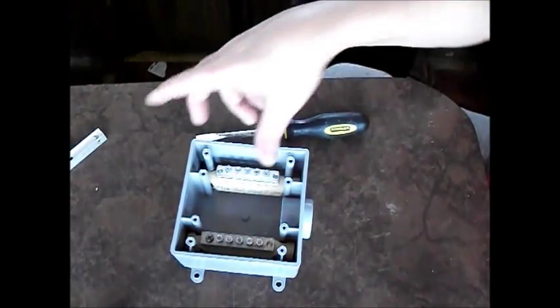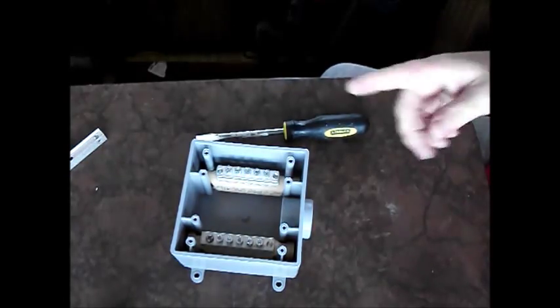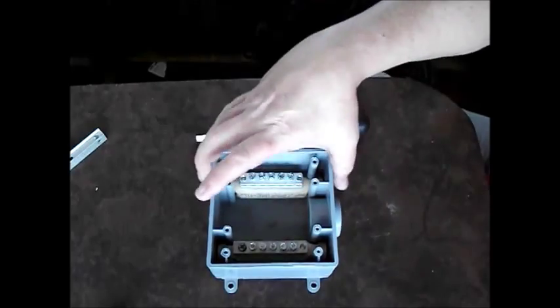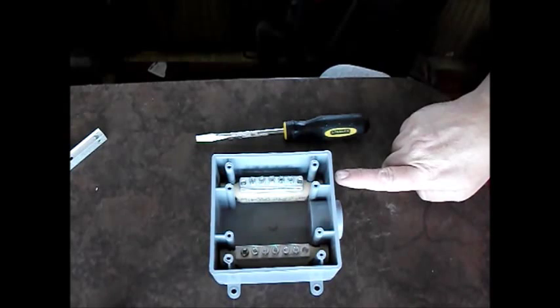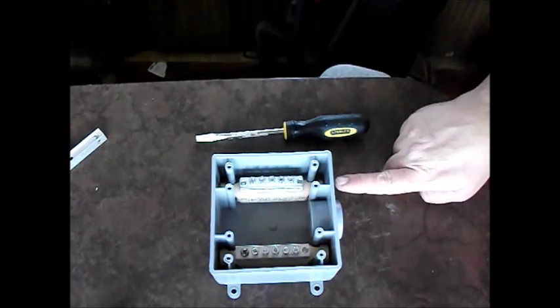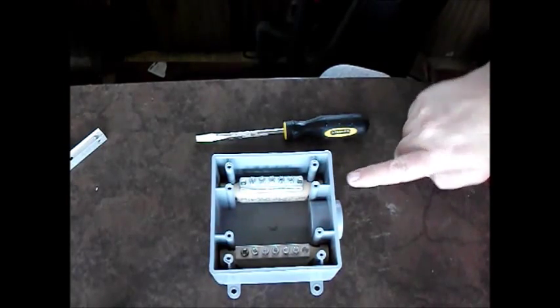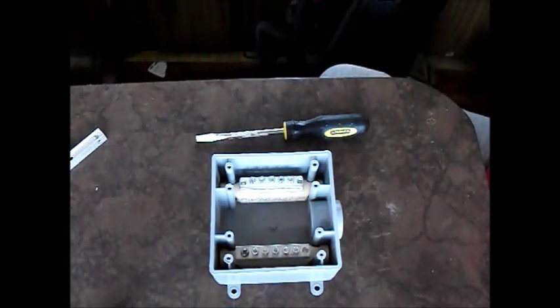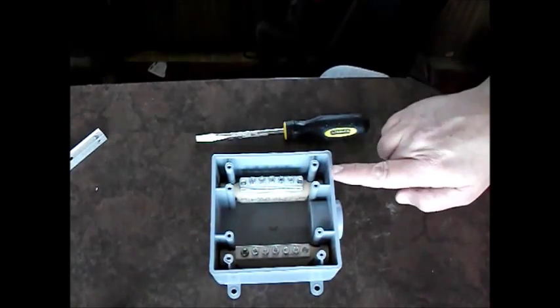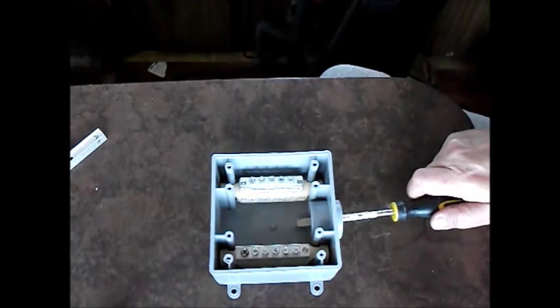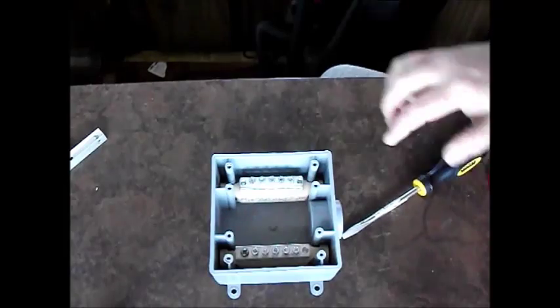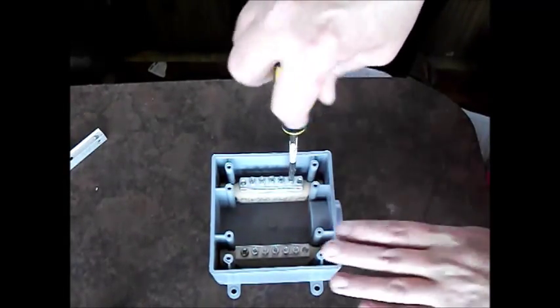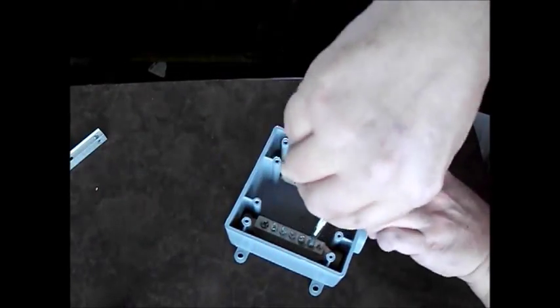The MC4 connectors are fine out in the weather. They're weatherproof, so we can just disconnect it like that. And that way, because that's going to take up a lot of space and this is a small box, I didn't want to put anything on the side. So what I'm planning on doing is drilling some holes the size of the wire in the bottom of this box along here. We'll have the wires come up through here and around and go into the bus bar. And then that way we'll make connection here at the bus bar, and then the wiring and everything from the house will come up through this point here from the conduit and it will go over and go to these two connections right here. We'll have them go to that connection there and have one go to this connection here.